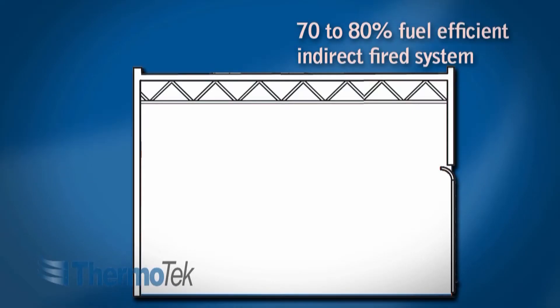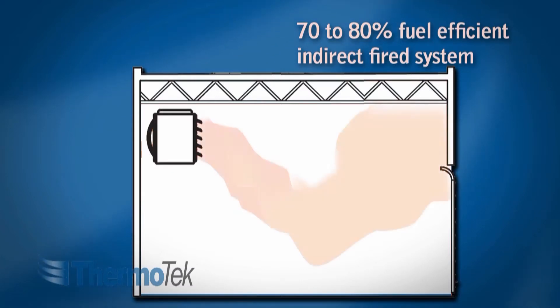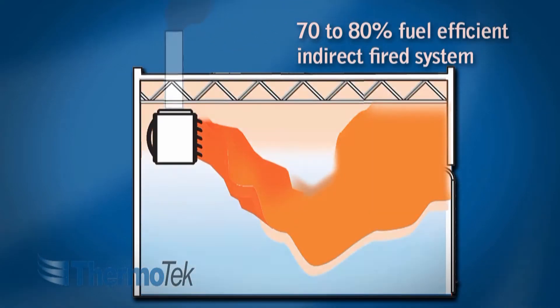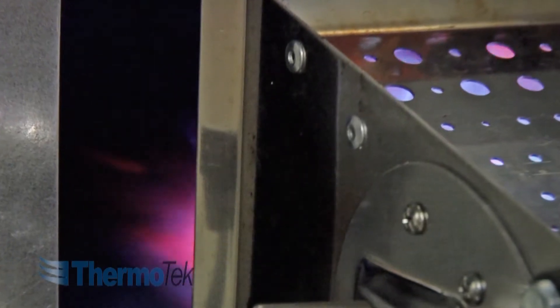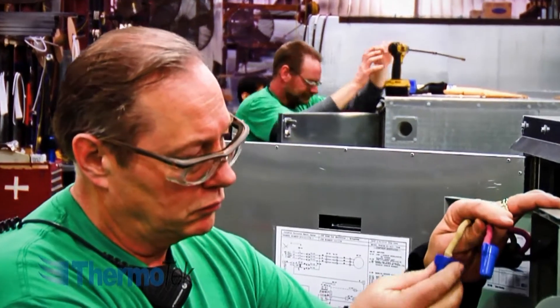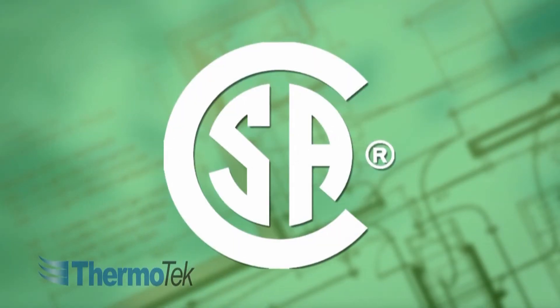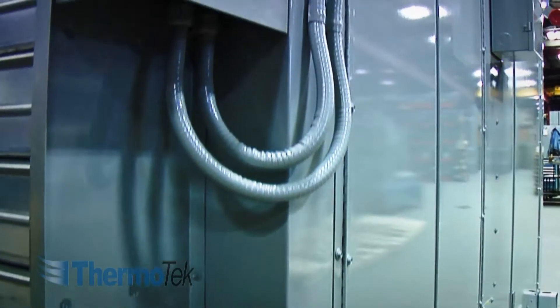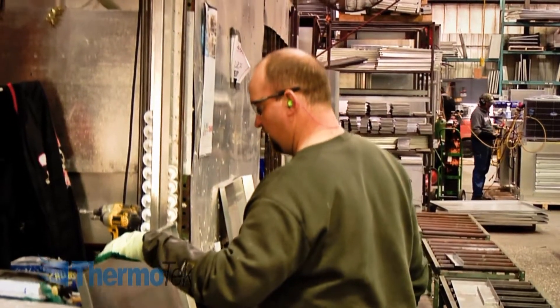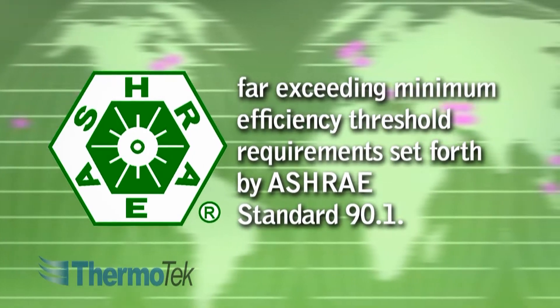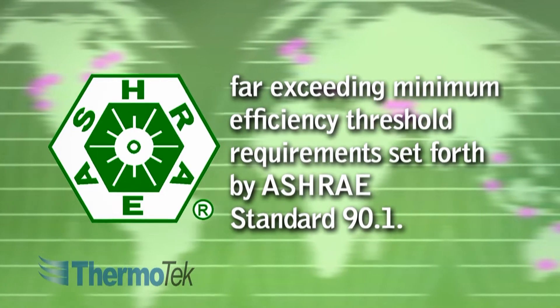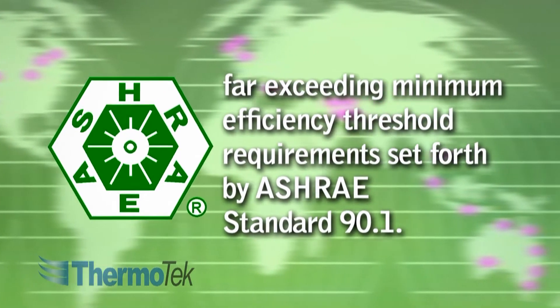Unlike a 70-80% fuel efficient indirect fired system that vents flue gases to the atmosphere, direct fired heating is environmentally clean and is tested to the highest standards for safe combustion rates under the ANSI and CSA guidelines. It's important to understand that direct fired heating is not only safe, but is widely considered a green technology in the industry today, and far exceeds the minimum efficiency threshold requirements set forth by ASHRAE Standard 90.1.